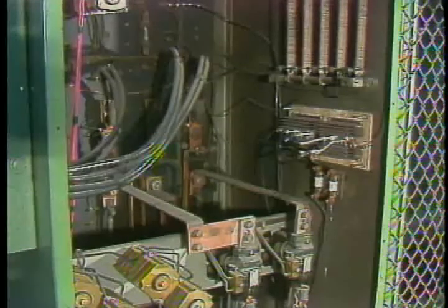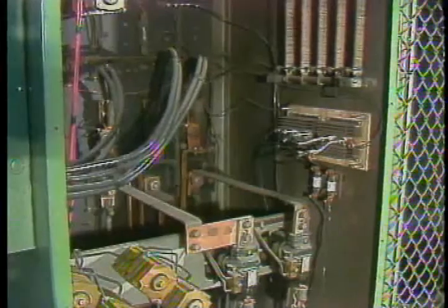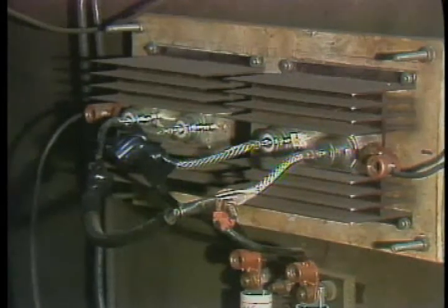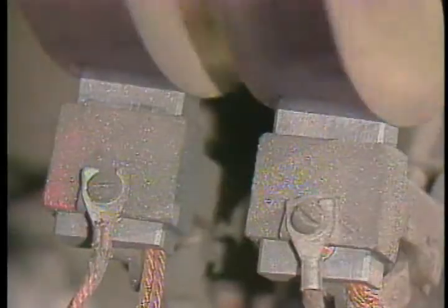Direct current for the rotor coils often comes from a controller outside the motor. A rectifier in the controller takes AC line voltage and turns it into DC. Brushes riding on slip rings in the motor conduct the DC to the rotor.